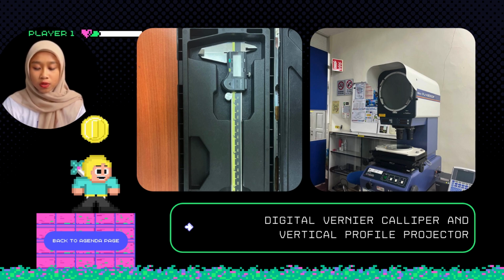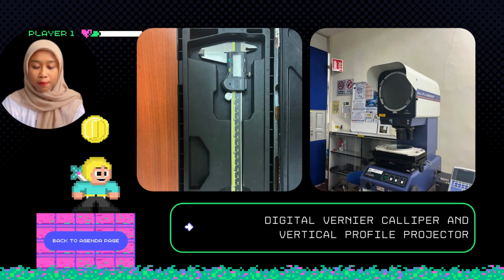Profile projector is widely used for complex shaped stampings, gears, cams, threads, and comparing the measured contour model. It's easy to use and highly efficient. It is commonly used as a measurement optical instrument. Thus, profile projector is widely used in major machinery manufacturing, including aviation and aerospace industry. The projector magnifies the profile of the specimen and displays this on the built-in projection screen. On this screen, there's typically a grid that can be rotated 360 degrees, so the XY axis of the screen can be aligned with a straight edge of the machine part to examine or measure.